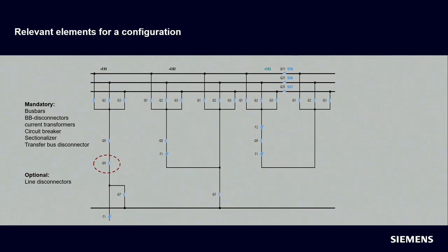Line disconnectors we need only in case we have a transfer bus. So here it's the case. In this case, as we have a transfer bus, we have to configure also the line disconnectors. And we also need the line disconnectors in case of parallel lines.